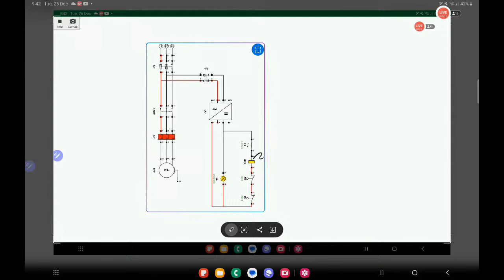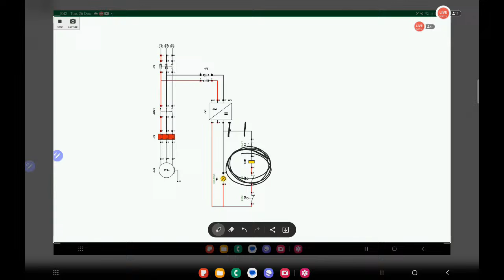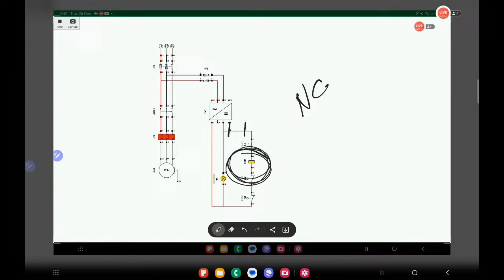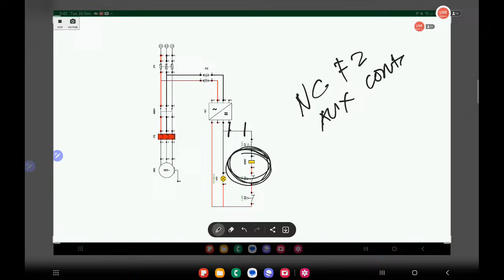So right now, let's say the limit switches satisfy our circuit diagram. Now we have this F2 that needs to stop the motor, right? See, the KM1 is still not stopping. So we need to put a breaking point wherein once this F2 is activated, then our KM1 itself will be deactivated. So the best point to put it is right before the start switch. We just need to put a normally closed F2 auxiliary contacts.